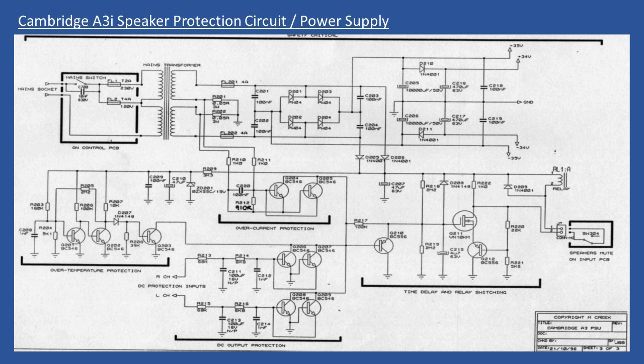Now what happens is, over time, those contacts, like any mechanical switch, and you could think of a conventional light switch that you switch on and off, as it operates thousands of times, as the contact makes the voltage and the current, it produces an arcing, and then over time the contact can become pitted or worn. Also, the relay will start to oxidize.